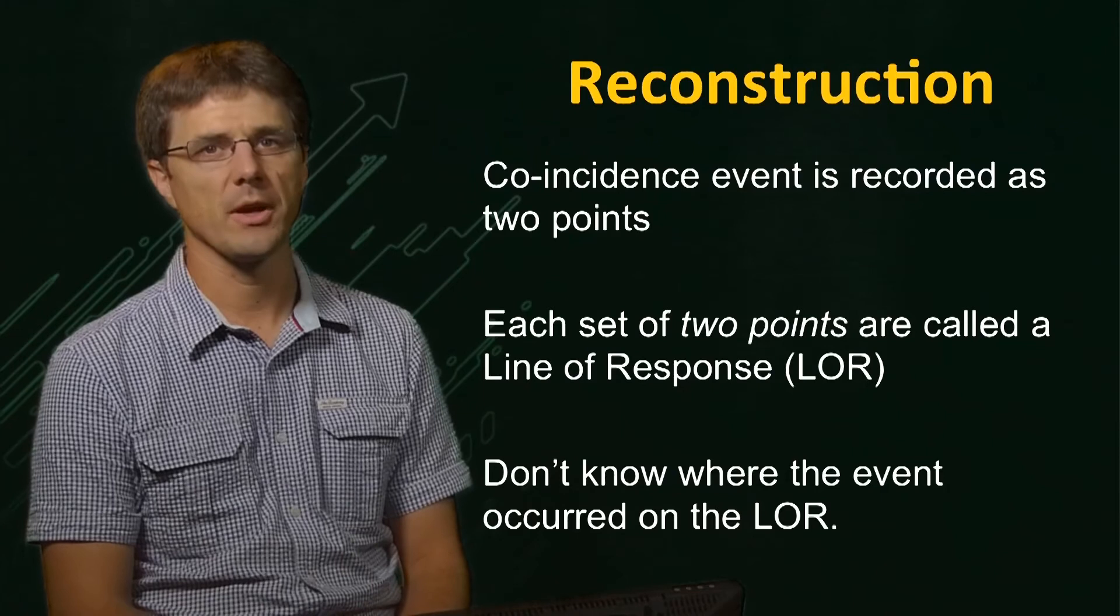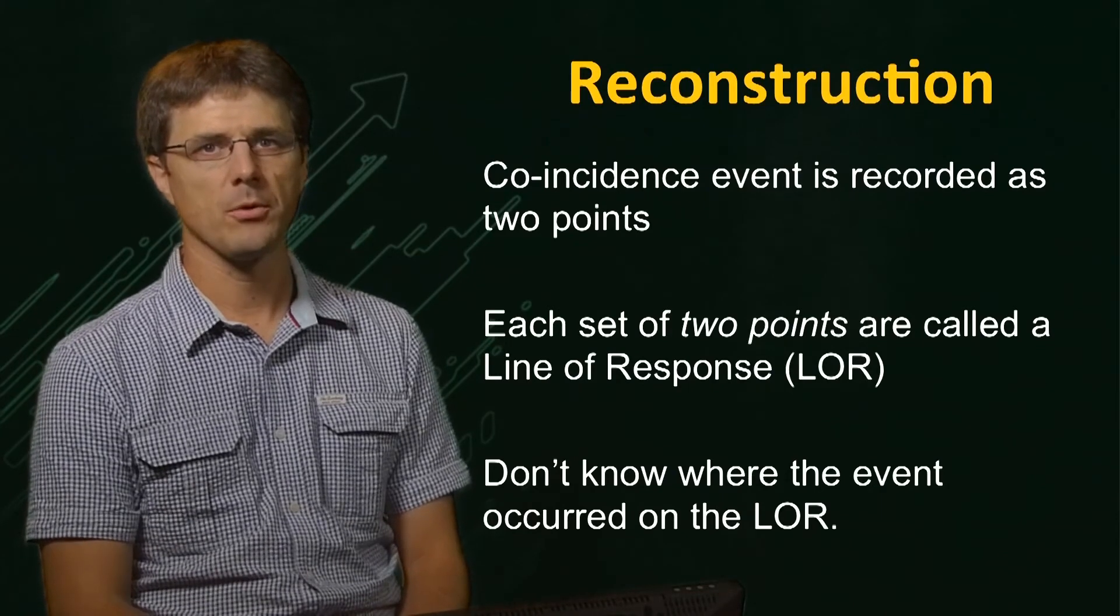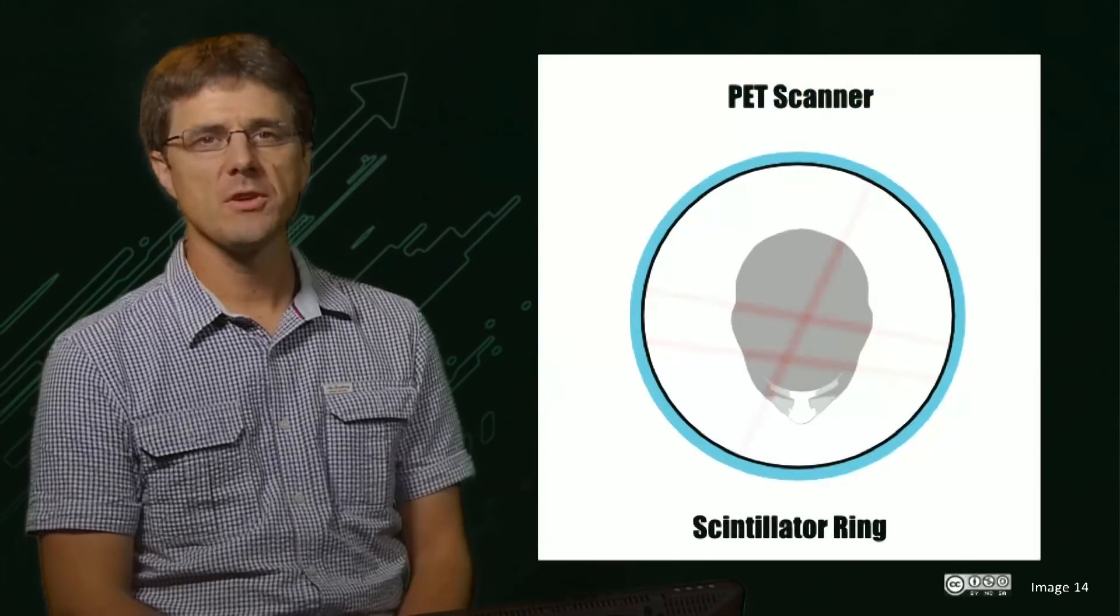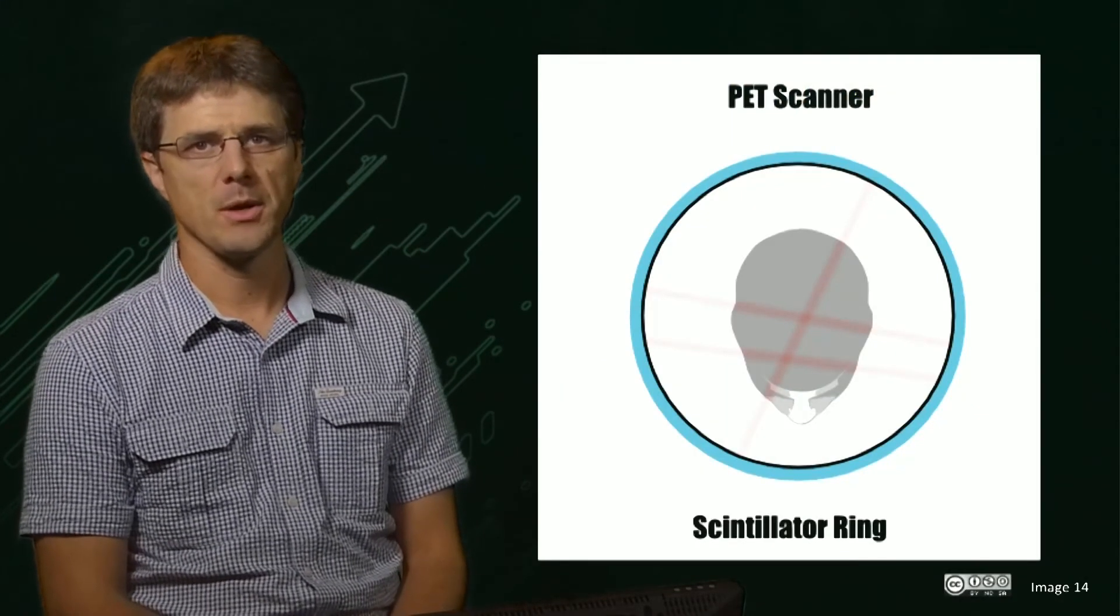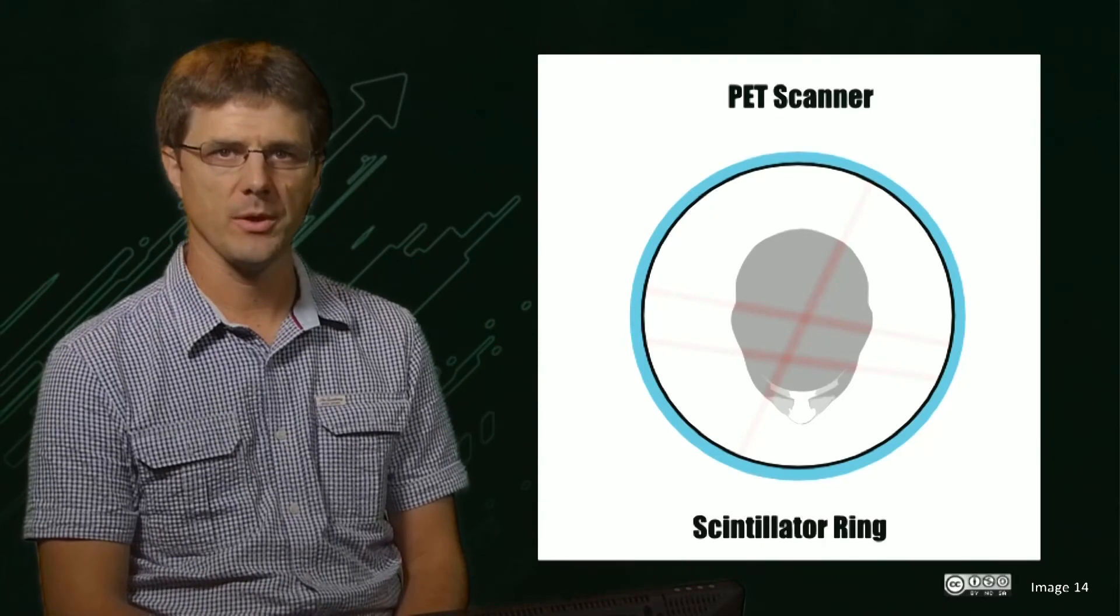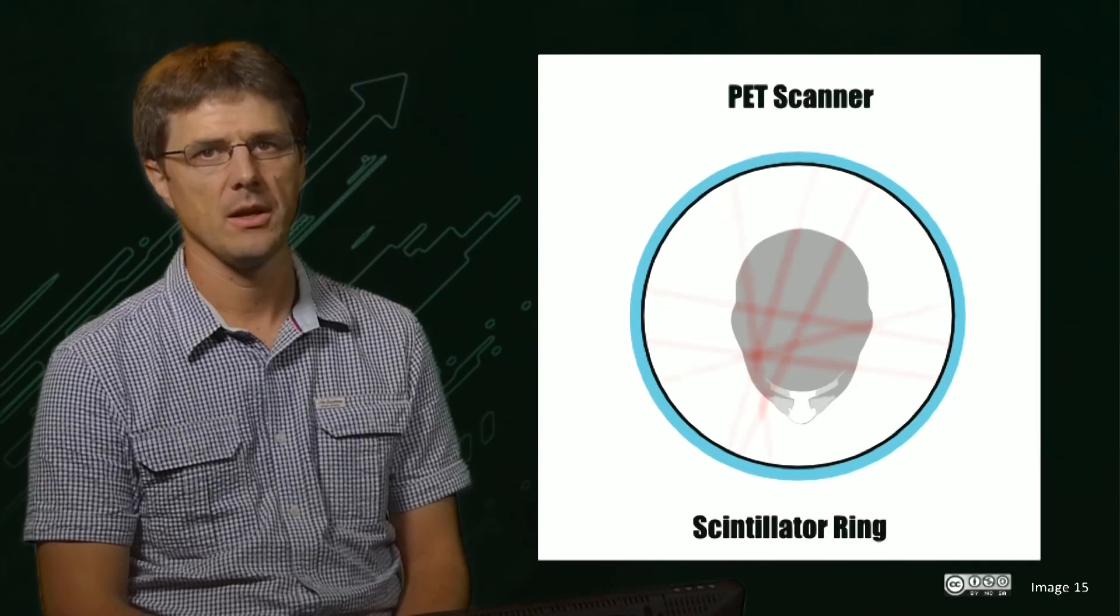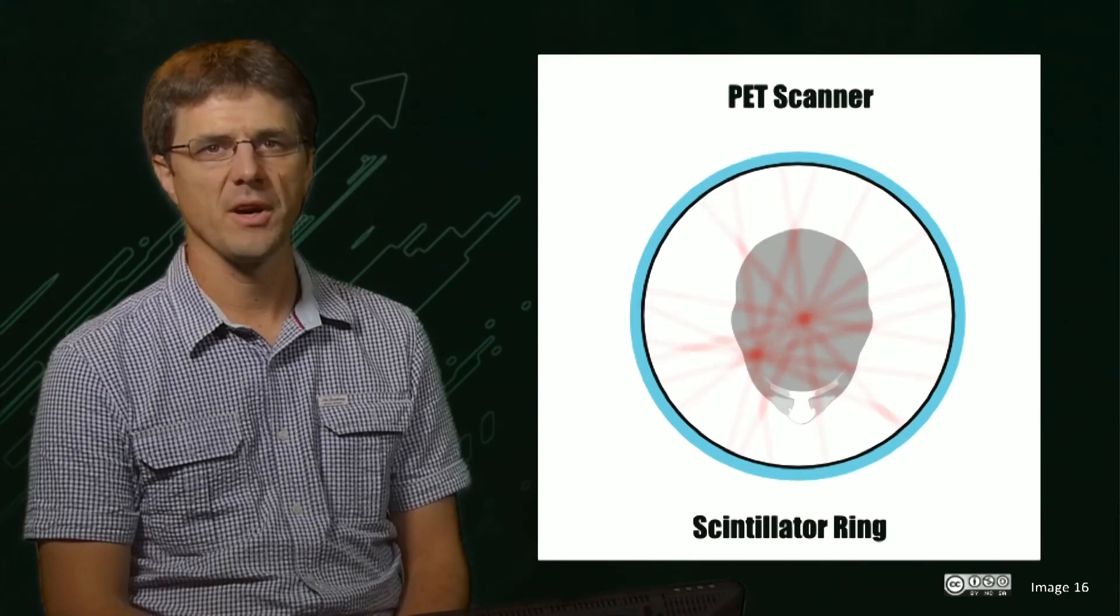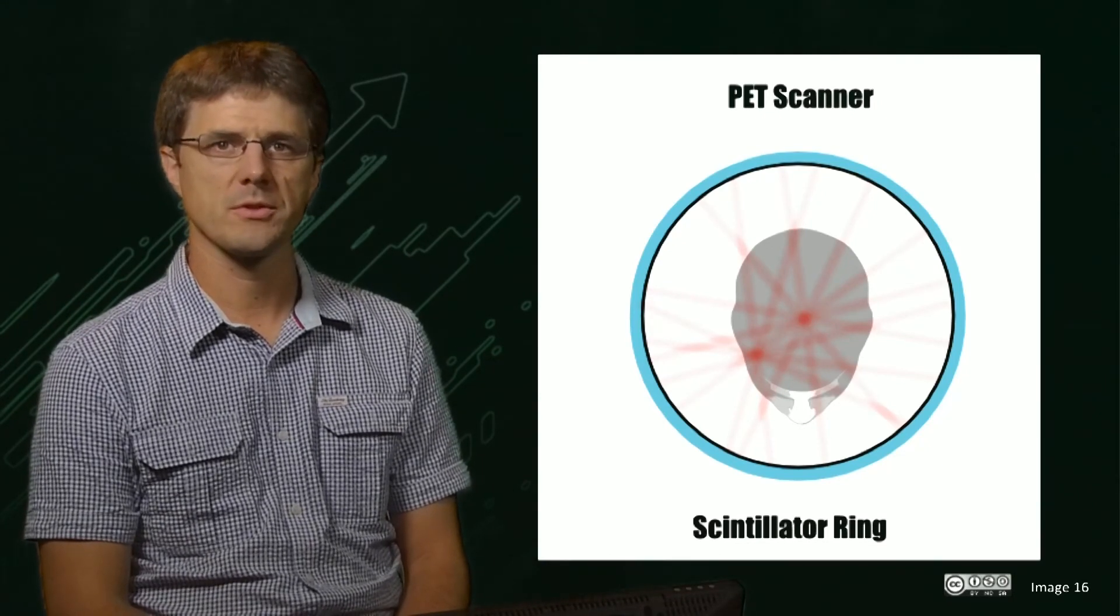These systems are called time-of-flight or TOF detectors, and operate on a timescale of approximately 3 nanoseconds. We can now visualize the reconstruction process by placing a probabilistic line between each of the two points from the coincidence event raw data. As we add more and more of these events, the result is a final probabilistic map of the source of the events.